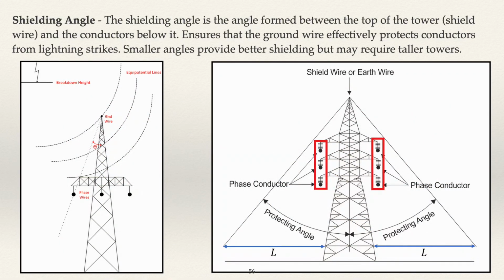Shielding angle. The shielding angle is the angle formed between the top of the tower, shield wire, and the conductors below it. Ensures that the ground wire effectively protects conductors from lightning strikes. Smaller angles provide better shielding, but may require taller towers.